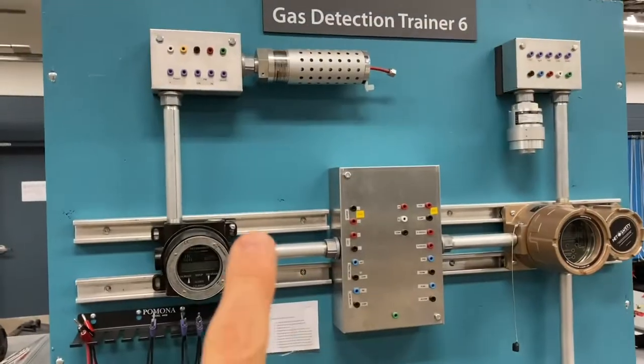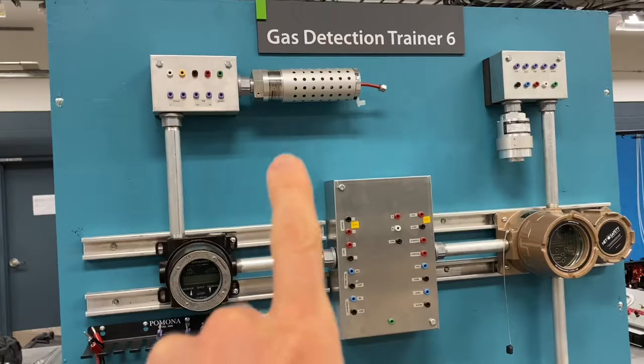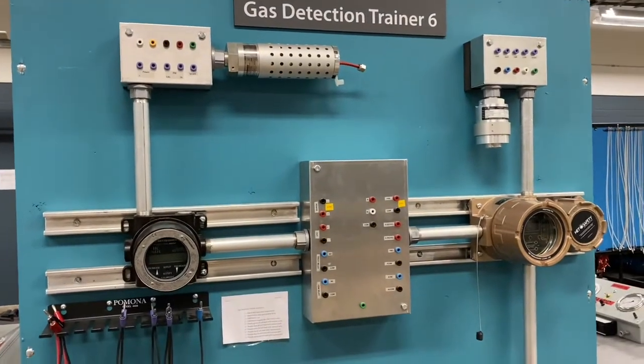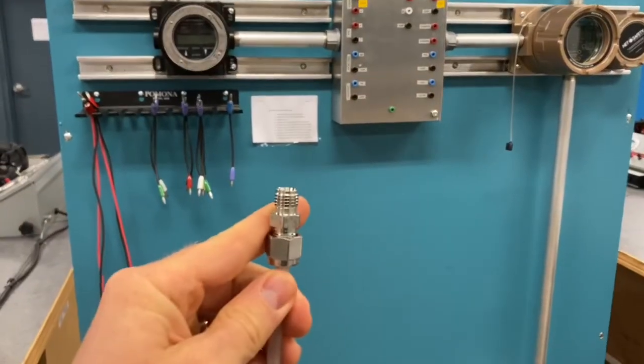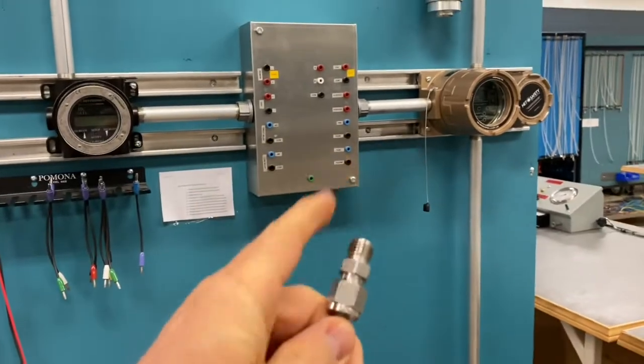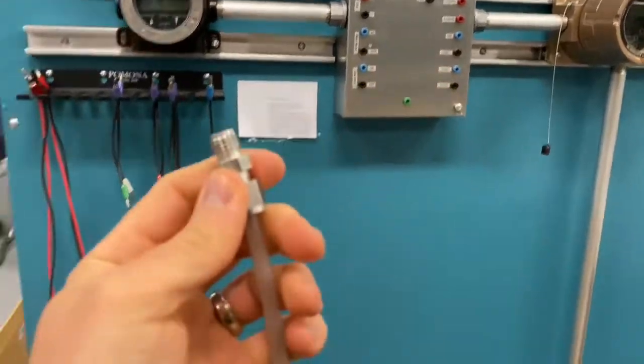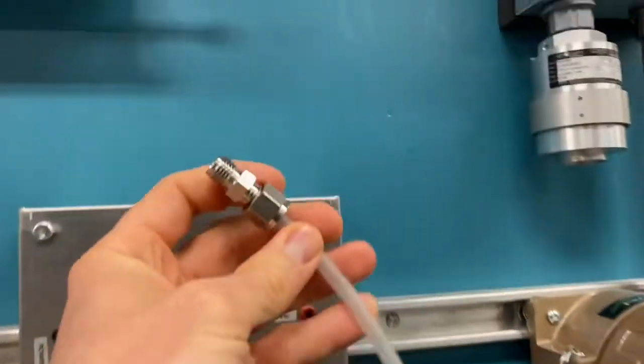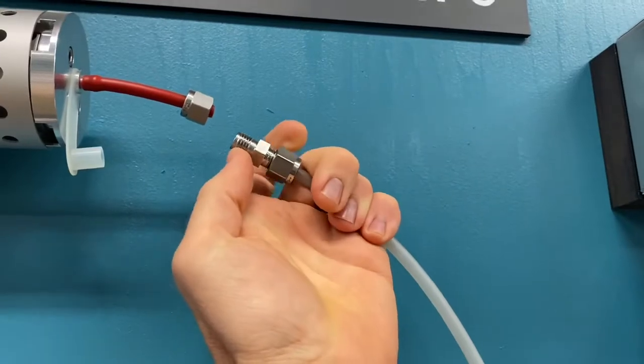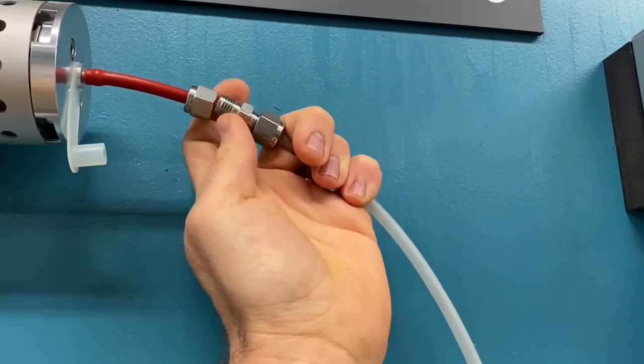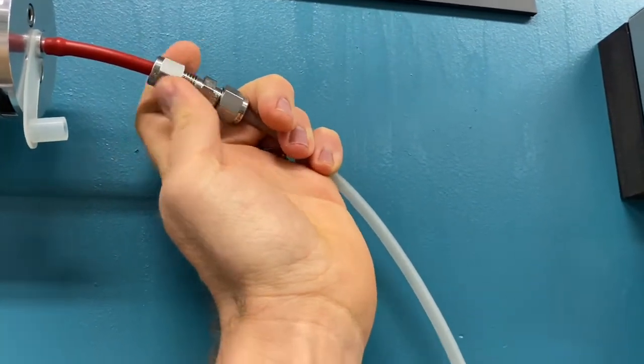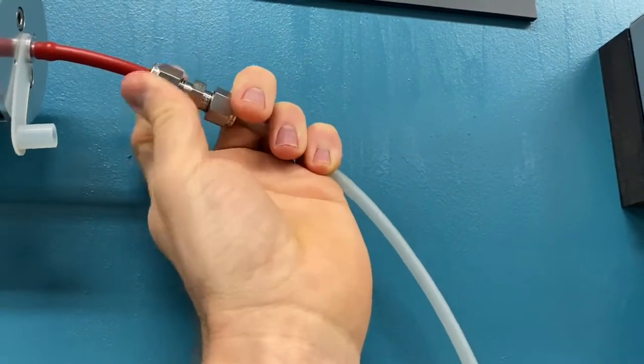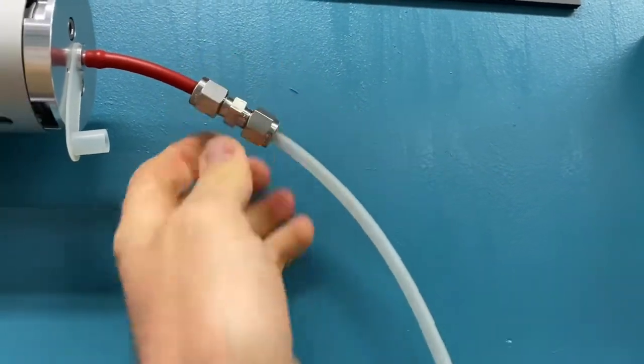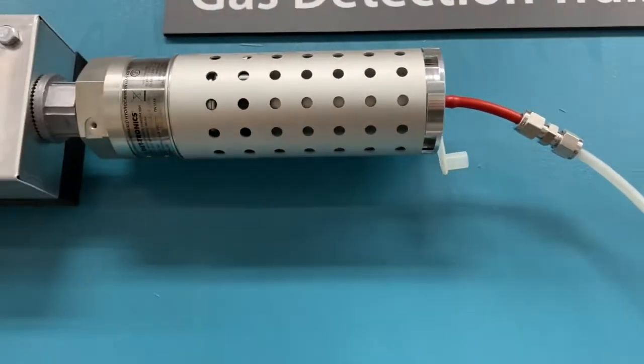So when we go to calibrate or check, actually we're just going to be checking this system here. When we go to check this system, instead of using that calibration cup that we were using for the Net Safety system over here, we're just going to remove that calibration cup. You can see that I've removed it and just set it on the counter here. We're going to remove that, and then this tubing union right here will just thread right on to this piece of plastic tubing that's just hung here, so that we can introduce the gas into the point sensor.